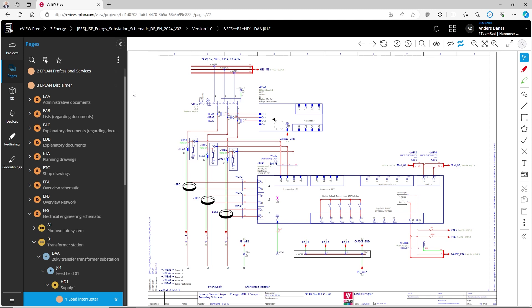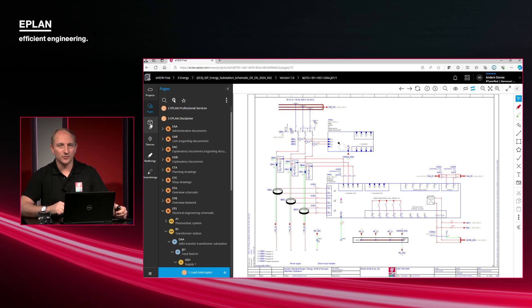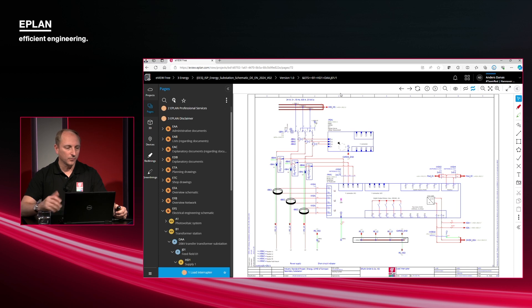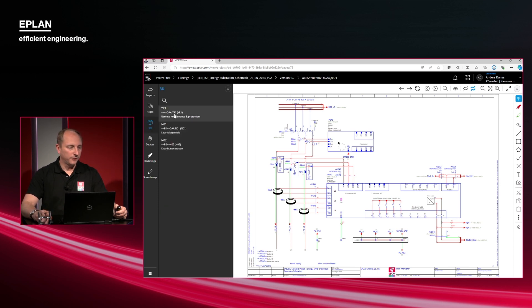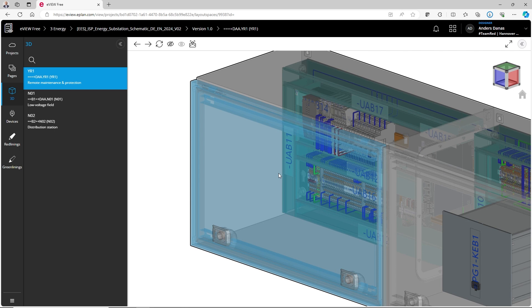Here we come directly into the page. Navigation is on the left side, where you can also view the project in 3D. You can see the devices that are there. If you have handled redlining — for example, if the field engineer identifies that he needs to replace a part — he can directly do the redlining to inform the engineer. This ensures up-to-date documentation in a digital way, rather than manually marking it on paper and bringing it back to the engineer. That's one of the big benefits of eView. And not only the 2D graphics, but you can also have a look at the actual cabinet, zoom in, see the actual components and wiring, and go into very fine detail for service and maintenance.